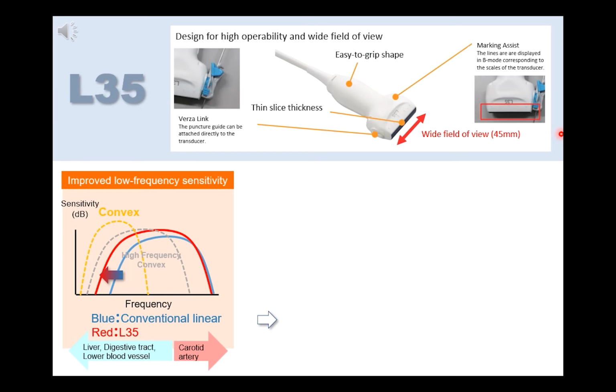This graph shows the frequency bandwidth and sensitivity of a currently used convex probe and a high-frequency convex probe. It may be slightly less sensitive, but by extending the frequency band to a higher point, a higher spatial resolution can be expected. On the other hand, a conventional linear probe was designed for a higher frequency range. It is inevitable that sensitivity decreases as the frequency increases, but sometimes, for example in abdominal cases, it is necessary to visualize to the far field.